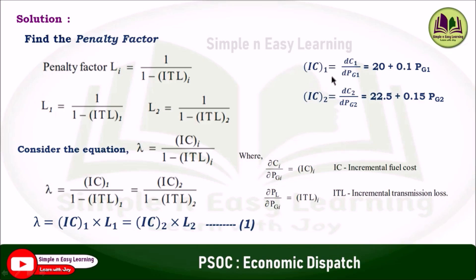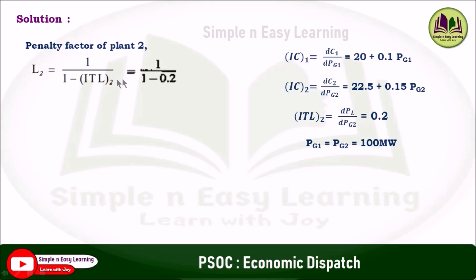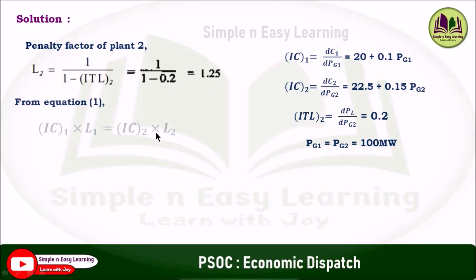In the problem, IC1 and IC2 are given, and the incremental transmission loss for plant 2 is given as 0.2. We will use these values to find the penalty factor for plant 1. First, we find the penalty factor for plant 2: L2 = 1 / (1 − ITL_2). Since ITL_2 = 0.2, L2 = 1 / (1 − 0.2) = 1.25. From equation 1: IC1 · L1 = IC2 · L2.